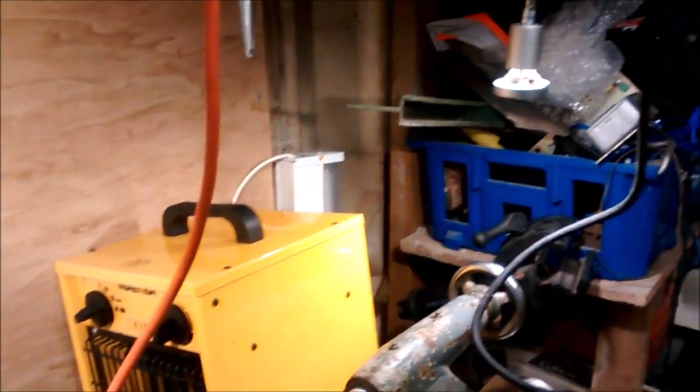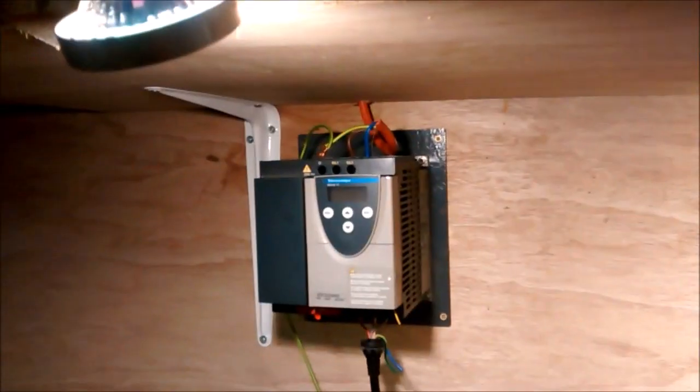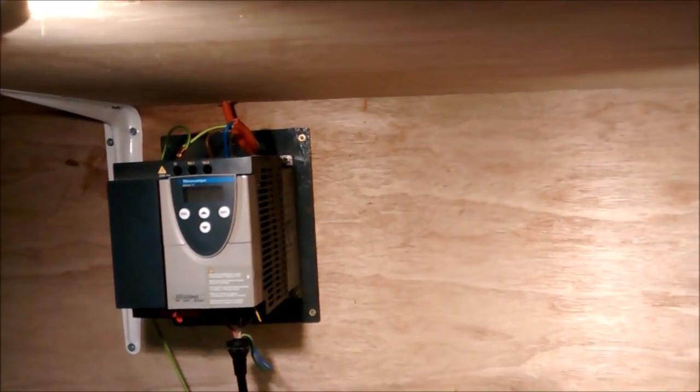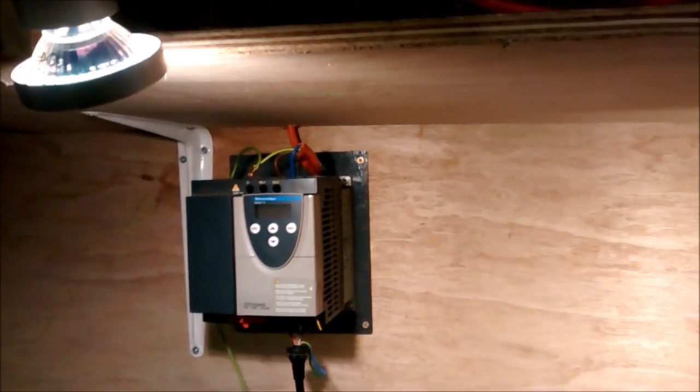I've had this fan heater on blowing just to reduce the humidity in here and warm it up. So I'm going to look out for now, see if I can find an isolation transformer and see what other options there are, because I do not want to remove the RCD or rewire so that there isn't an RCD.